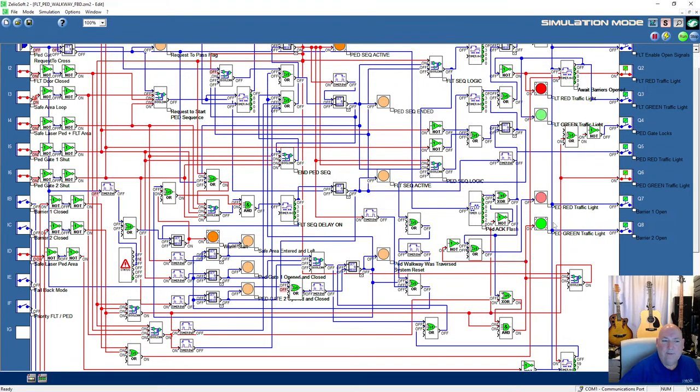Right. So, we're in that mode. Then we don't do anything. We're counting down. Yeah, that's good. Then we go through sequence, open the PED gate, safe area. And still counting down, that's okay, but we'll be in this area, so we'll stop the countdown. Then we'll close the gate, open the other gate, leave the safe area, close the other gate, and leave the safe area. Now it's going to time out. That opens after half a second, so that was right.